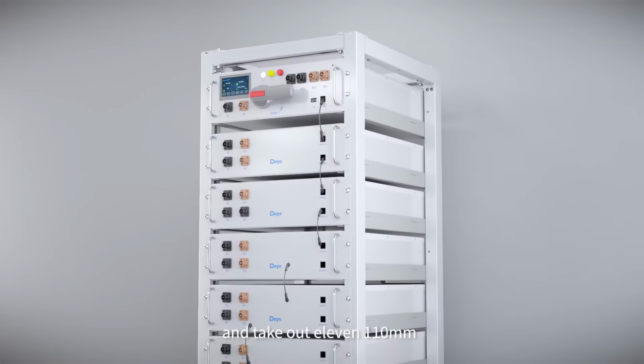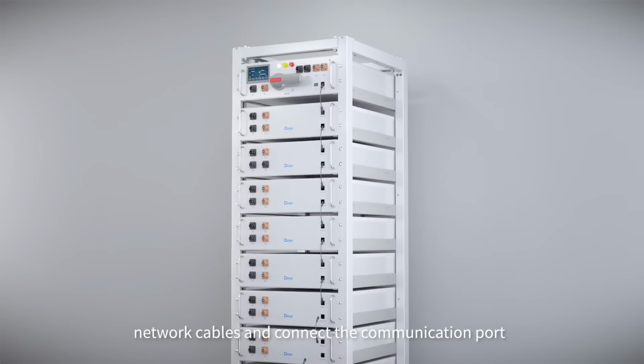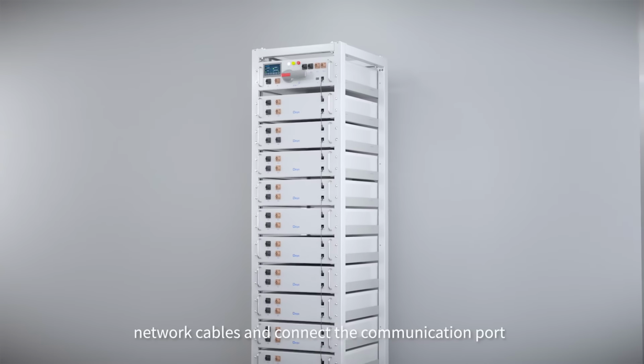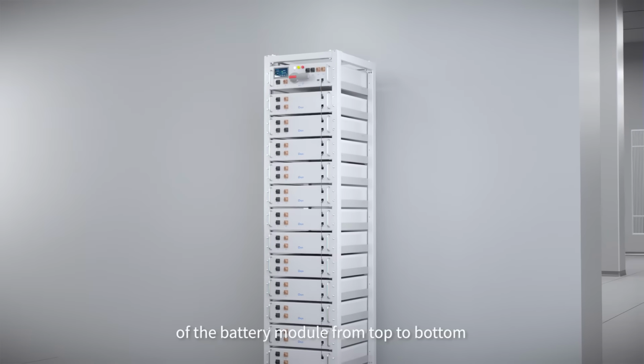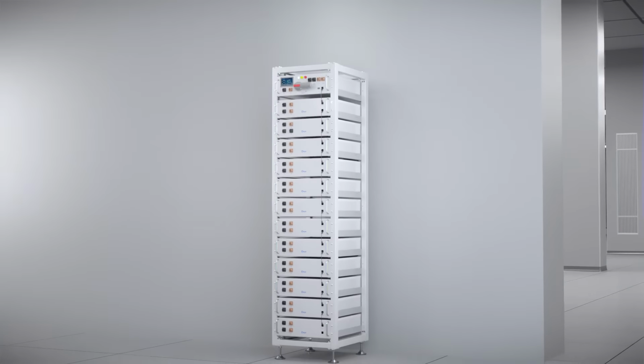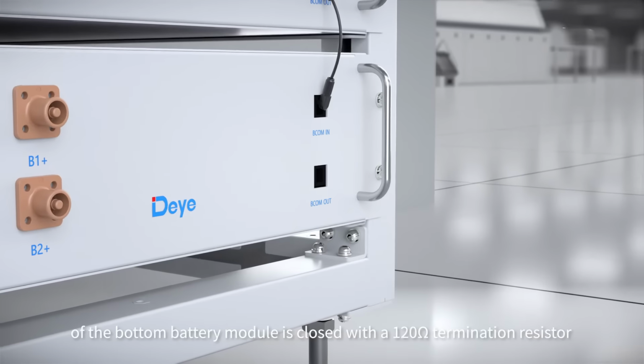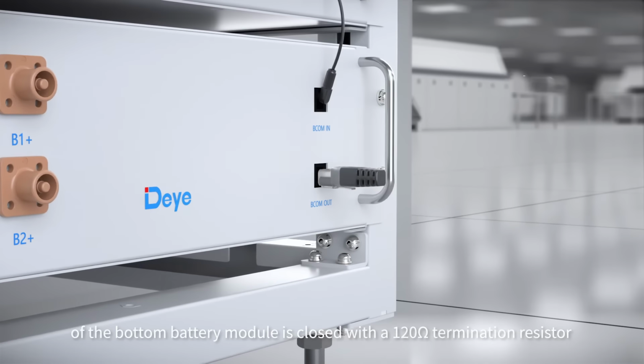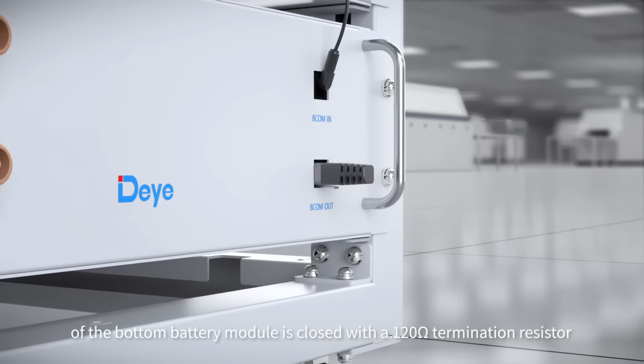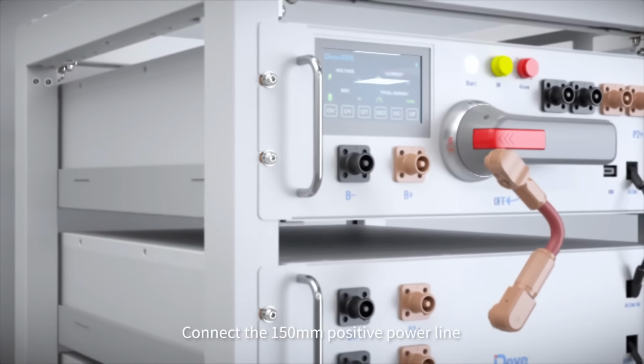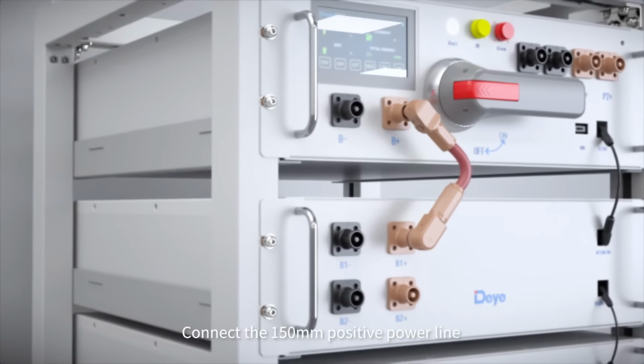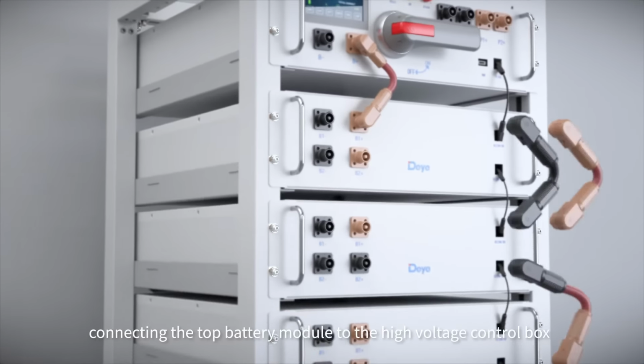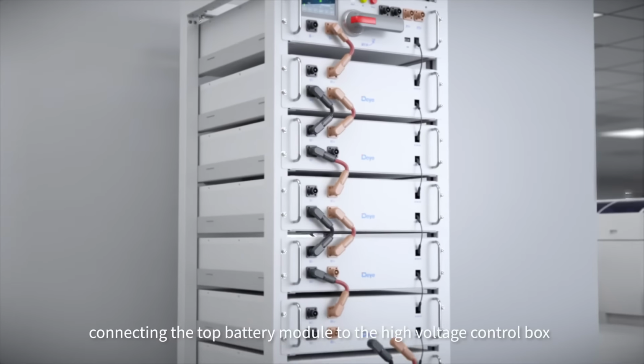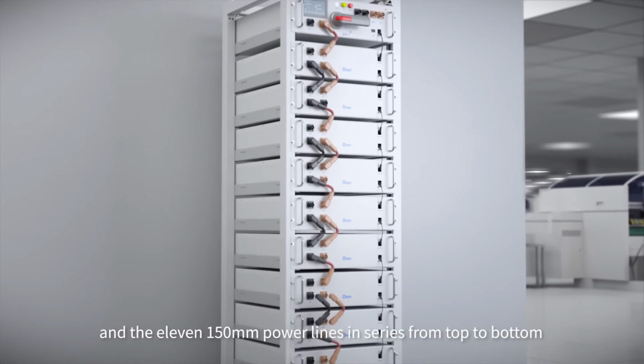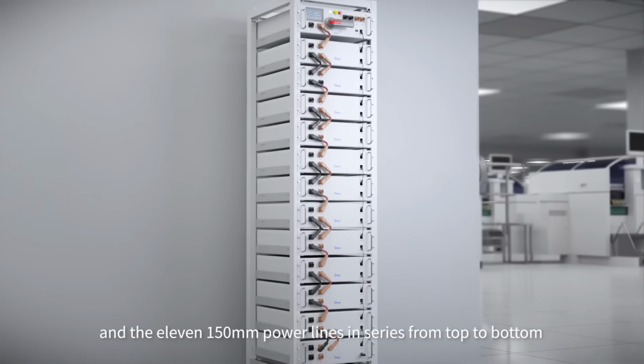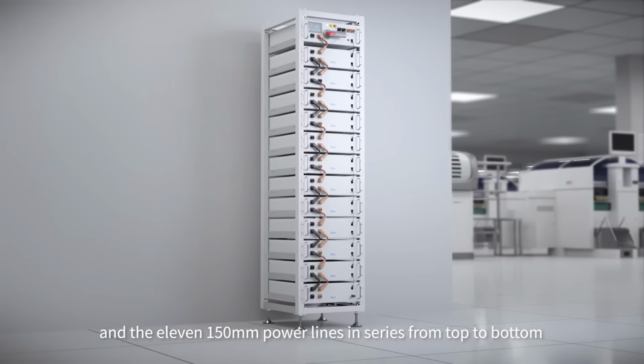box. And take out 11 110mm network cables and connect the communication port of the battery module from top to bottom. The communication port of the bottom battery module is closed with a 120 ohm termination resistor. Connect the 150mm positive power line, connecting the top battery module to the high voltage control box, and the 11 150mm power lines in series from top to bottom.